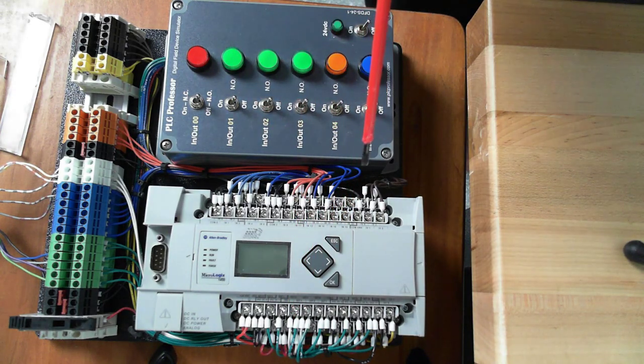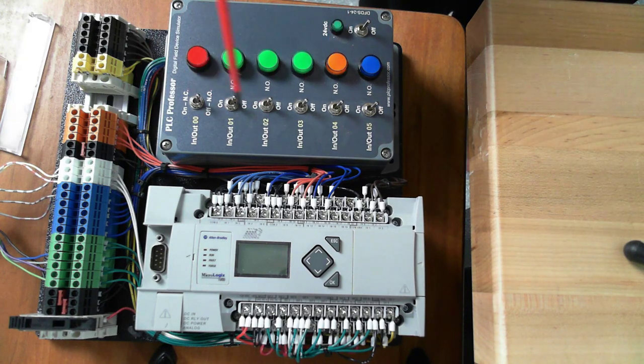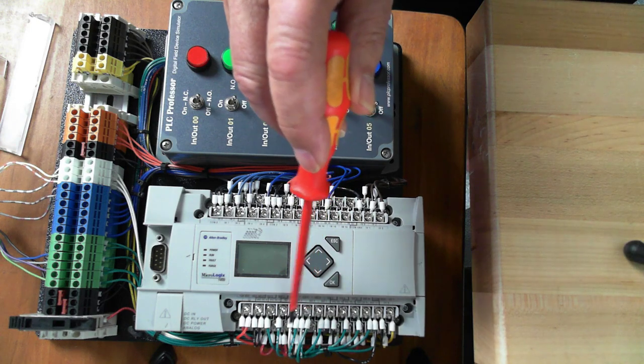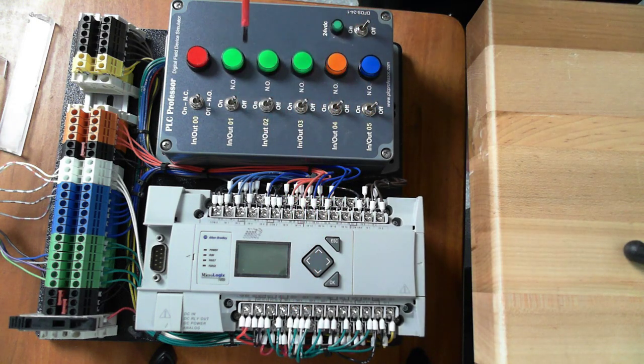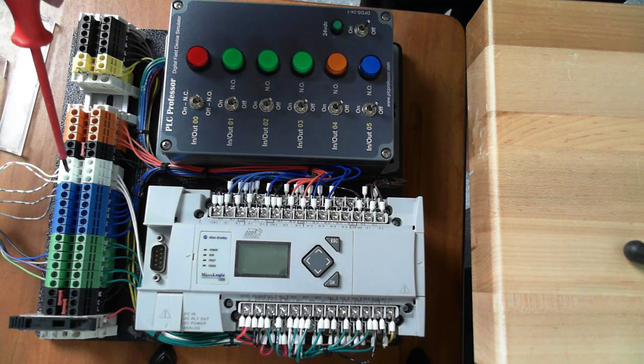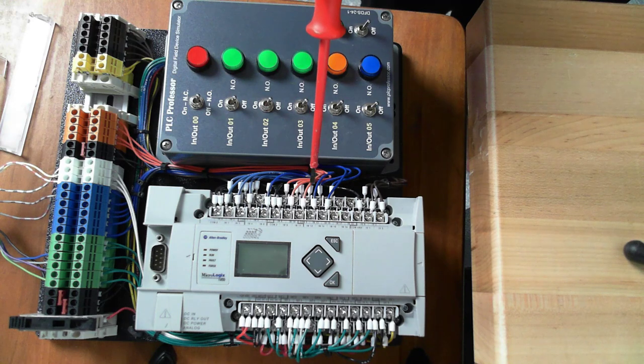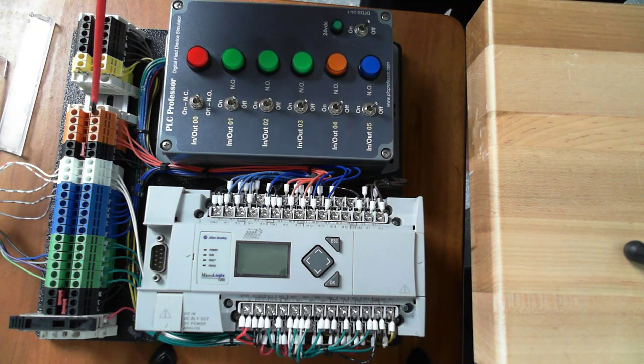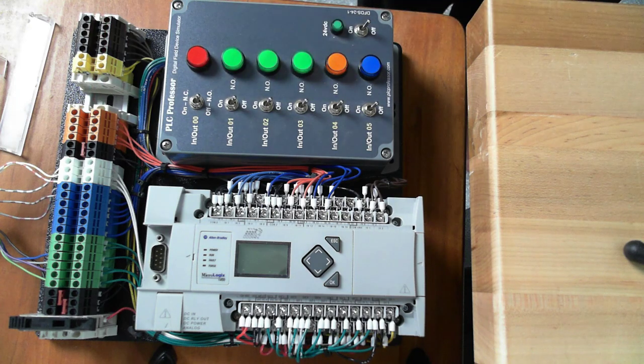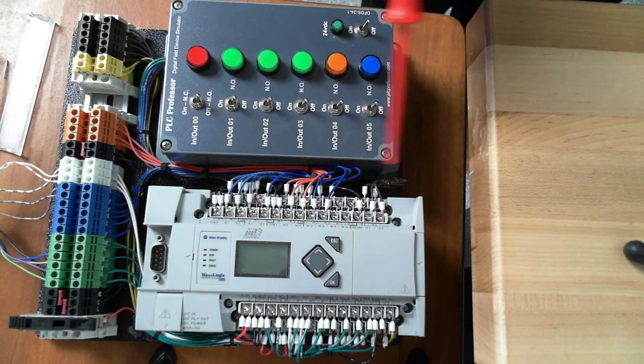Now, you think, well, is there a conflict there? No, there's not, because it has to do with how you program this, what it's trying to do, and what you have connected at the other end of these green wires. If it happens to be lights, so what if they go off and on when you're running your PTO or PWM code over here? And here you see we have four orange wires. Those go to the high-speed counter inputs. So you see this does get pretty congested.